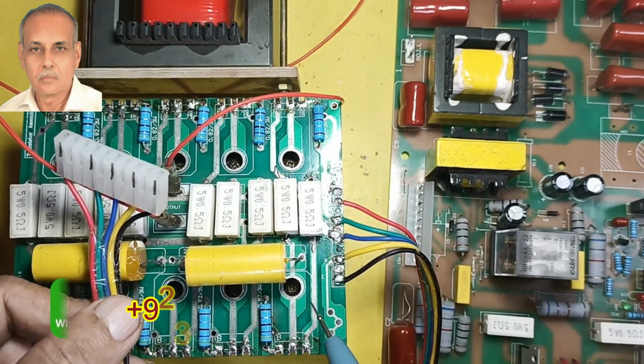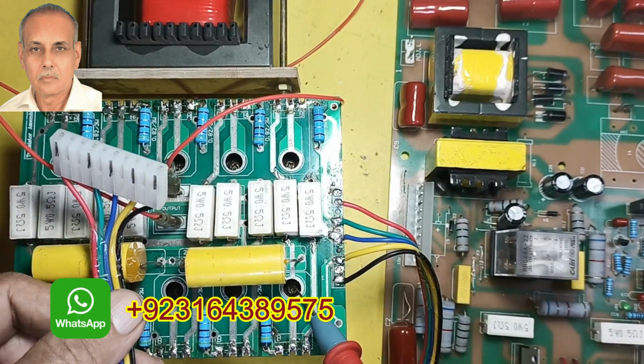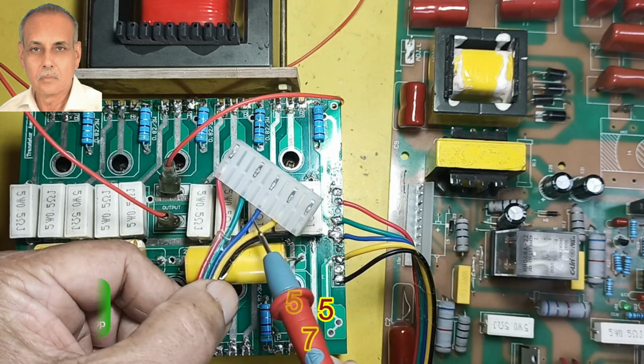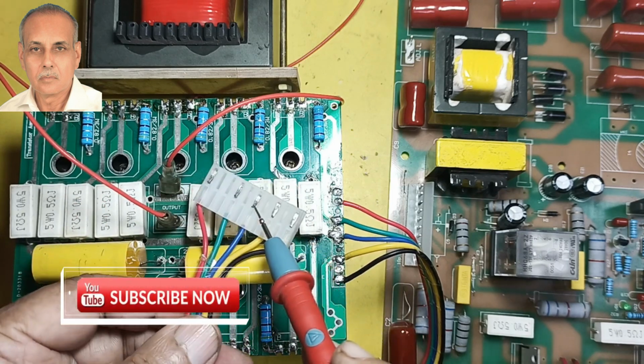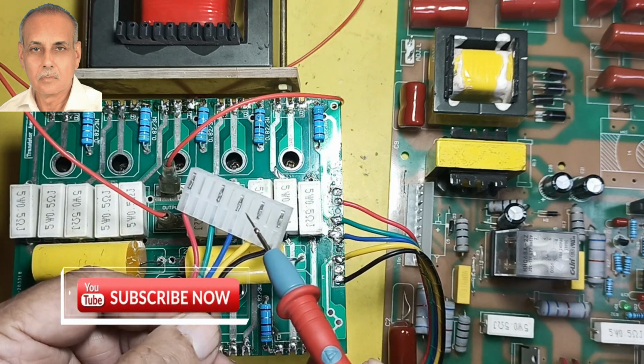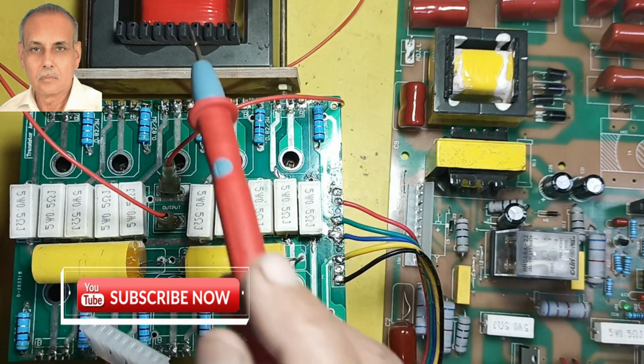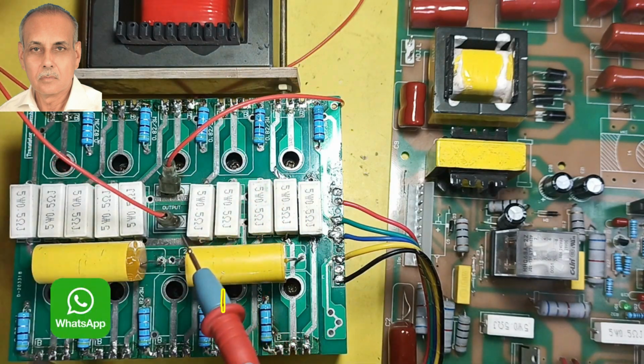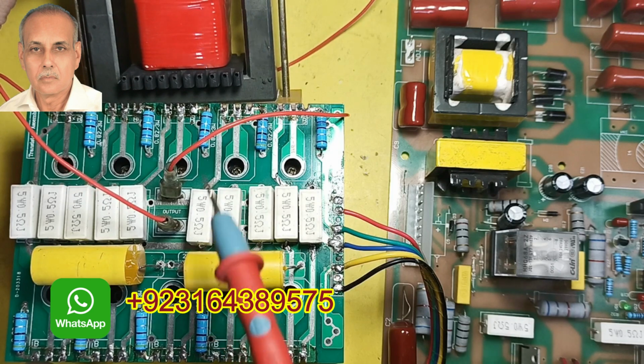From here, generated AC is supplied to the output transformer through a series capacitor of 20 UF. At this point the DC is converted to high frequency AC, the frequency of which is the desired ultrasonic frequency. Its voltage becomes very high in the output transformer, so that the transducer can generate the required mechanical power.